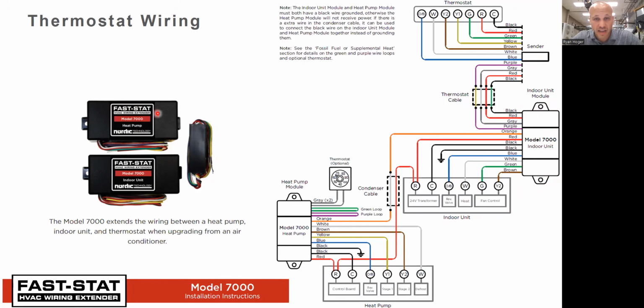The second piece of that is this outdoor one that goes out at your heat pump outside on the roof. And what that does, same thing, this box takes some of those wires that we got the thermostat signal from and digitally combines them into a communicating signal. He basically sends an email. This is not actually email, I'm just using it as a concept. Sends an email to the outdoor unit that says, hey, I want this, this, or that to turn on. And they talk to each other. And this allows you to get that done. These boxes cost a couple $100. So usually you just run new wire, but sometimes you can't, and you'll need to do something like this.